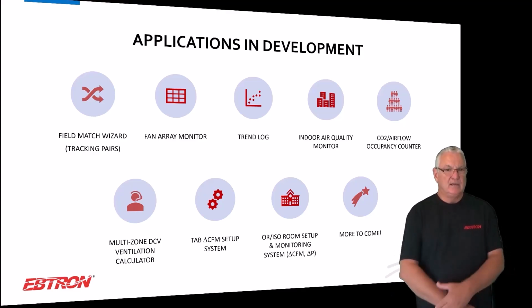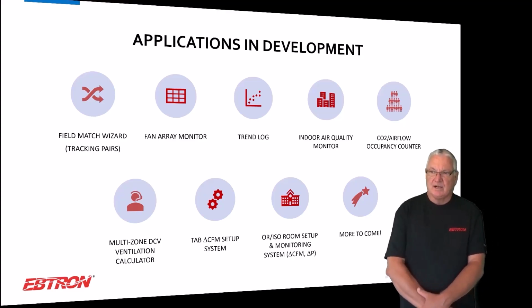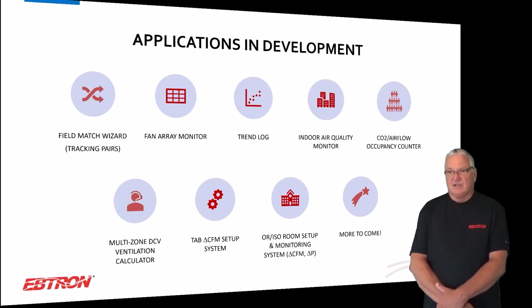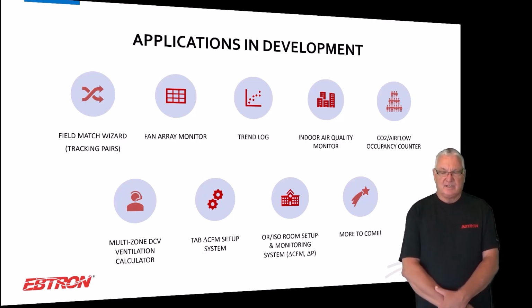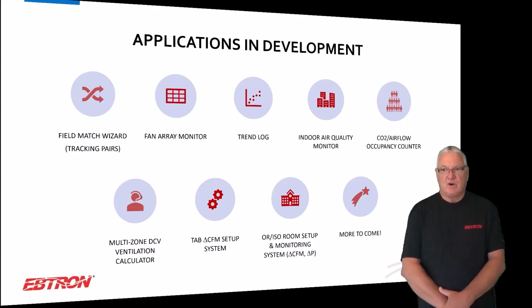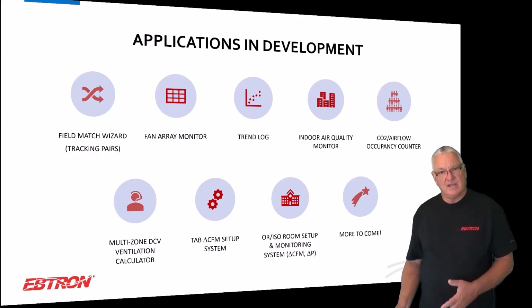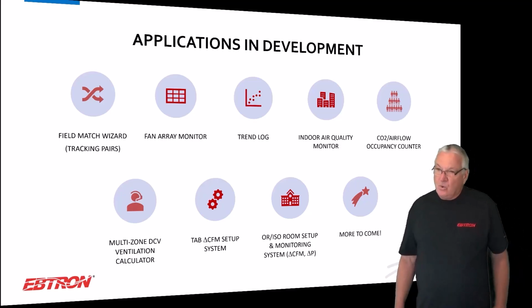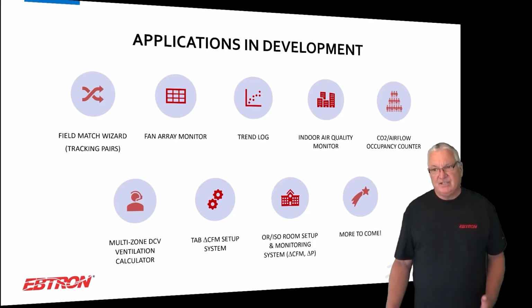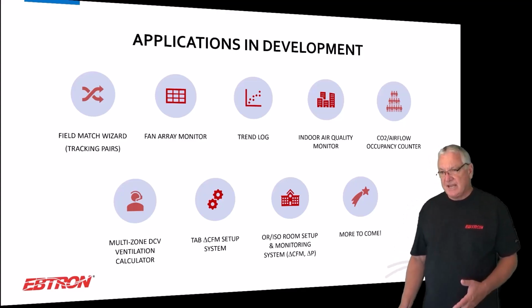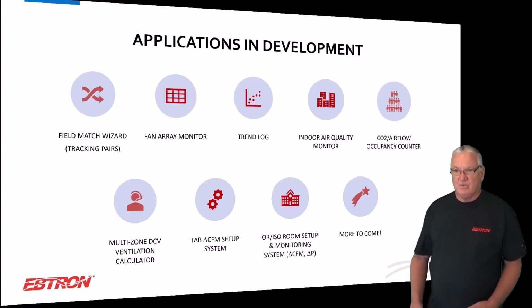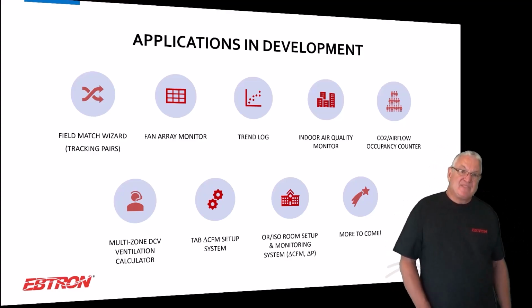the road, okay? The Field Match Wizard app. We find that there's a lot of cases where people put these things in the supply and the return of an air handler in particular, and they go 100% closed loop, and they want to match one to the other. Maybe one's not in a good location or a marginal location, or you actually want to tighten them up. We can show you that if you use this Field Match Wizard and you have low leakage dampers, you can bring these flow meters to within 0.5% of each other. So there are some advantages of doing that for pressurization.